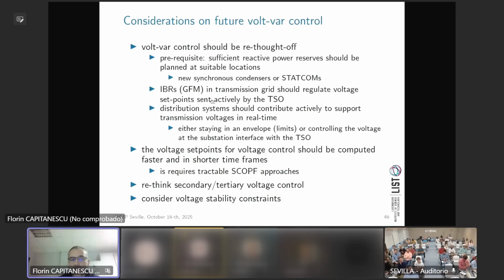IBRs in grid-forming mode in transmission should regulate voltage set points sent by the TSO, which is not the case today. Today, from own experience, they either operate at unity power factor or at a given power factor depending on active power production.